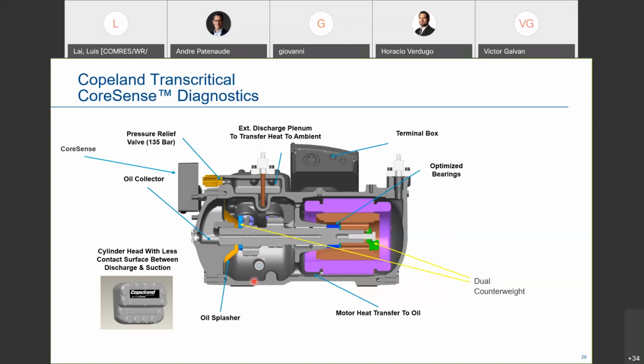Another feature of the 4MTL is it's got a balanced crankshaft. So you can see the green counterweight on the back end, the motor end, and the blue counterweight on the crank end. And that's unique to the CO2 transcritical compressor. And I didn't have one here, but when you compare vibration, even in sound, of our compressor versus Bitzer, it has a lower vibration rate, it has lower sound.